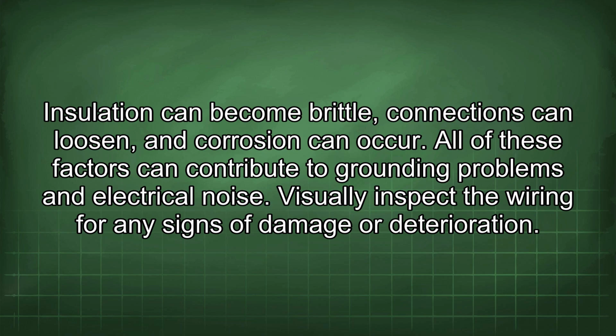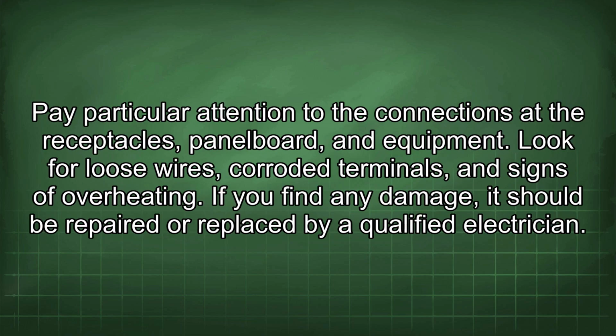Visually inspect the wiring for any signs of damage or deterioration. Pay particular attention to the connections at the receptacles, panel board, and equipment. Look for loose wires, corroded terminals, and signs of overheating. If you find any damage, it should be repaired or replaced by a qualified electrician.